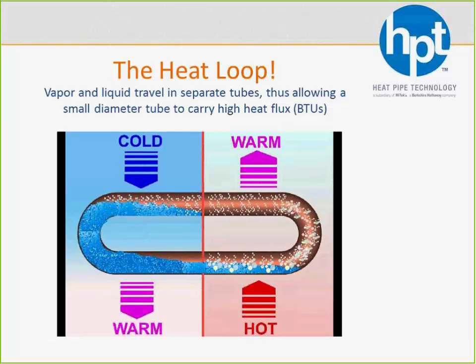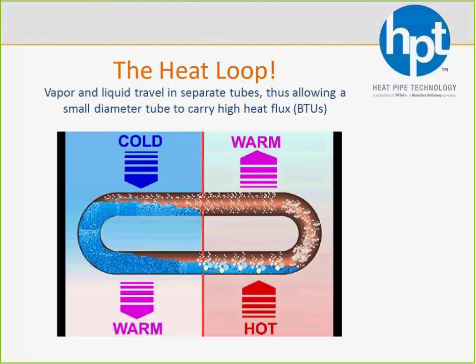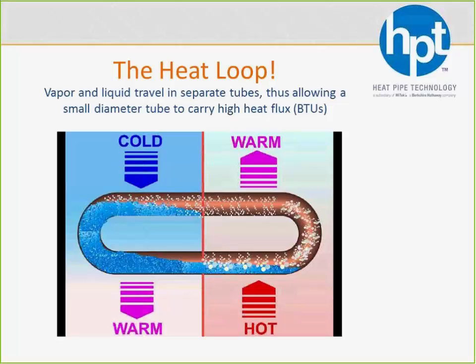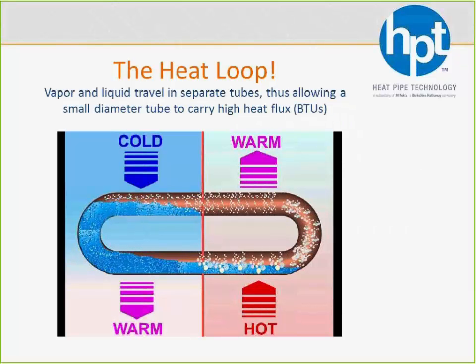Smaller tubes with the same amount of rows allows us to add less static pressure to the system. We get a little bit more heat transfer out of it, and you'll find that some other heat pipes need what they call a tilt mechanism when the season changes to make sure that liquid's always running downhill. We don't need that. Because of this loop circuit, the refrigerant's just going to change directions all by itself.